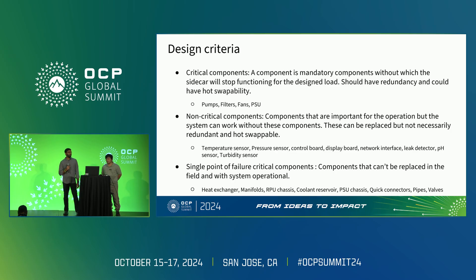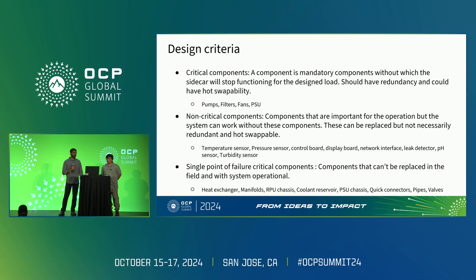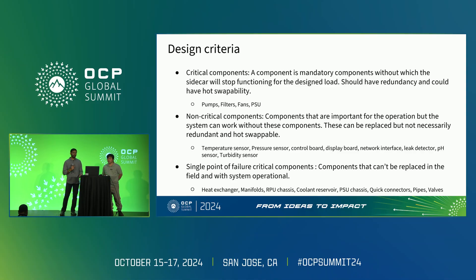We also want to define a design criteria, categorized into critical components, non-critical components, and single point of failure components. Critical components are mandatory — without them you cannot run a sidecar — such as pumps, filters, fans, and PSUs. These can be hot-swappable and have redundancy built into the design so that you can replace them without stopping operations while remaining fully operational.